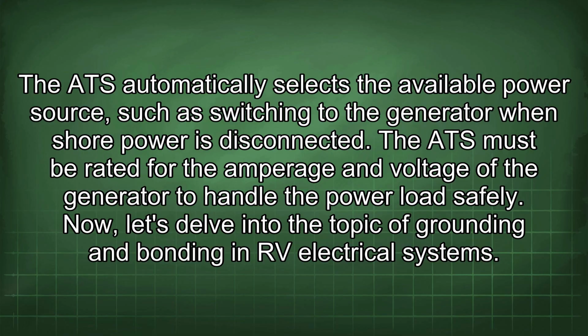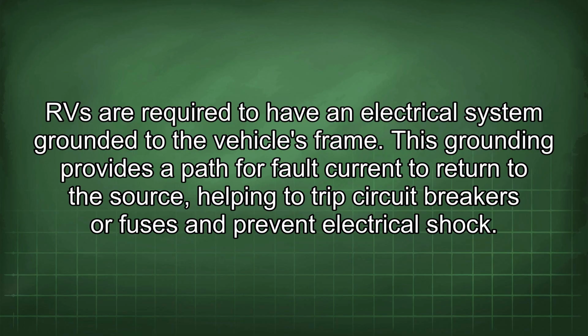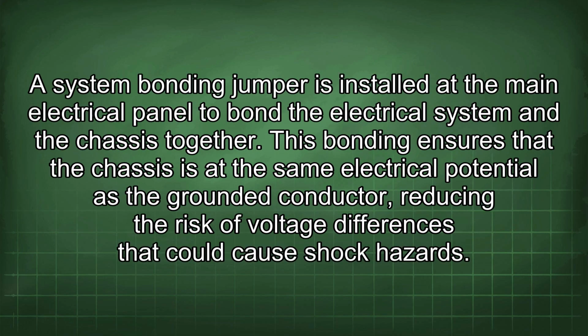Now let's delve into the topic of grounding and bonding in RV electrical systems. RVs are required to have an electrical system grounded to the vehicle's frame. This grounding provides a path for fault current to return to the source, helping to trip circuit breakers or fuses and prevent electrical shock. A system bonding jumper is installed at the main electrical panel to bond the electrical system and the chassis together. This bonding ensures that the chassis is at the same electrical potential as the grounded conductor, reducing the risk of voltage differences that could cause shock hazards.